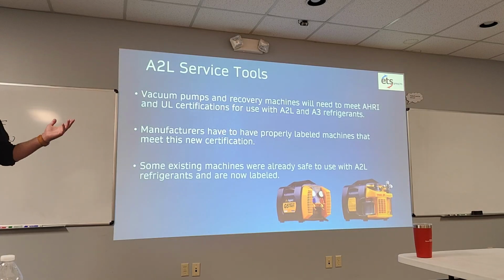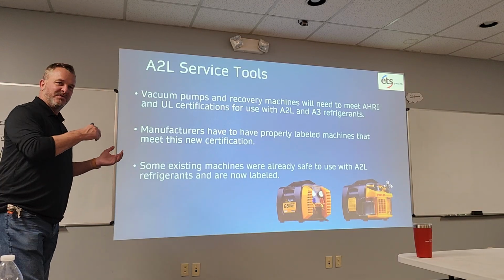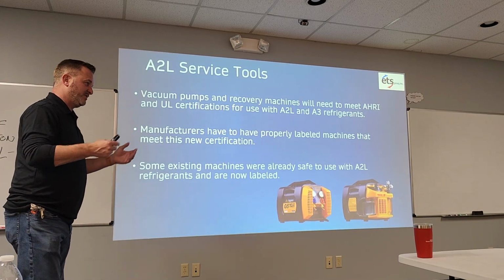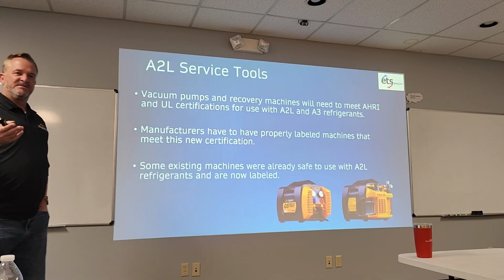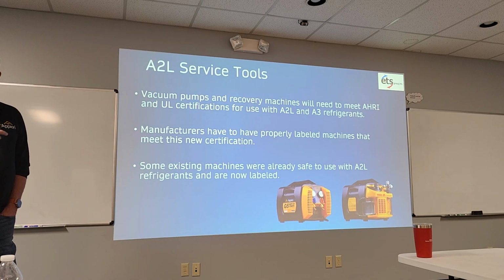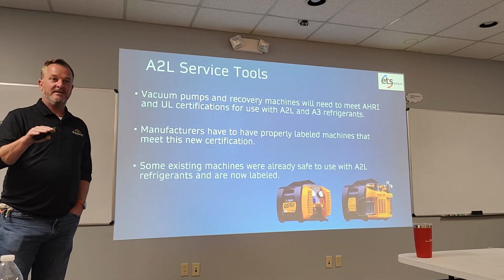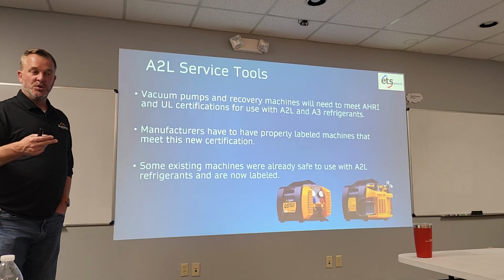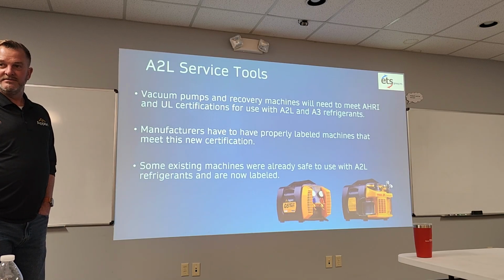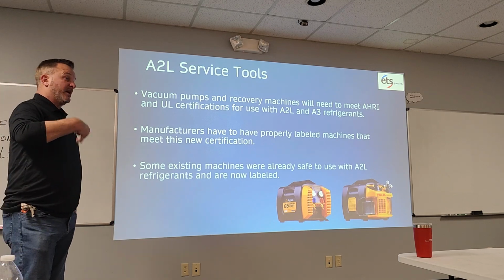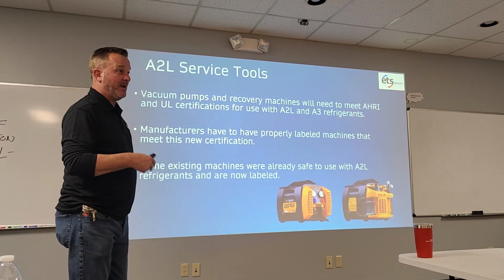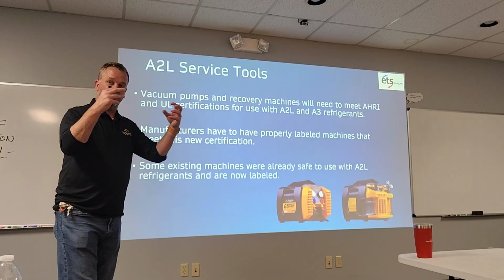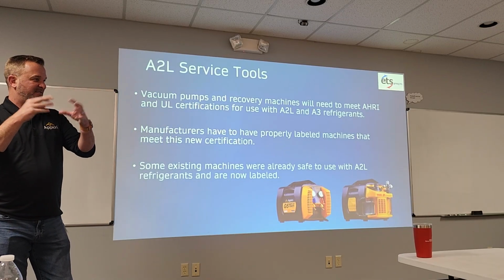With vacuum pumps, it doesn't matter too much because we've gotten all the refrigerant out already, then we purge with gas and put the vacuum pump on. People always ask me about ammonia systems too, can you recover ammonia with a recovery machine? We recommend not doing that. But can you use a vacuum pump on an ammonia system afterward? Yes, you can, we just recommend flushing that vacuum pump out after, because any ammonia or leftovers sitting inside will tear it all apart.